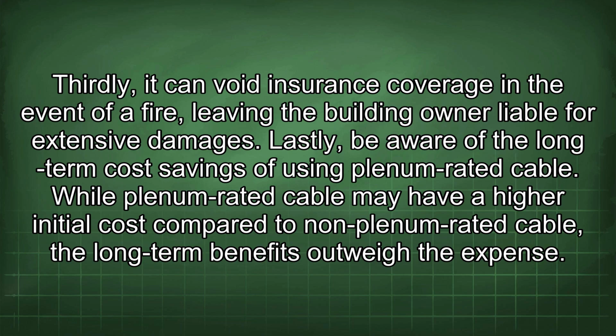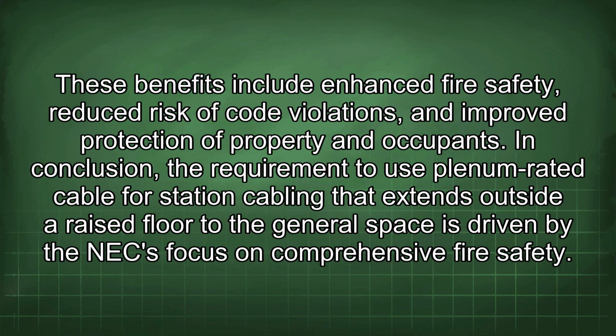While plenum-rated cable may have a higher initial cost compared to non-plenum-rated cable, the long-term benefits outweigh the expense. These benefits include enhanced fire safety, reduced risk of code violations, and improved protection of property and occupants. In conclusion, the requirement to use plenum-rated cable for station cabling that extends outside a raised floor to the general space is driven by the NEC focus on comprehensive fire safety.